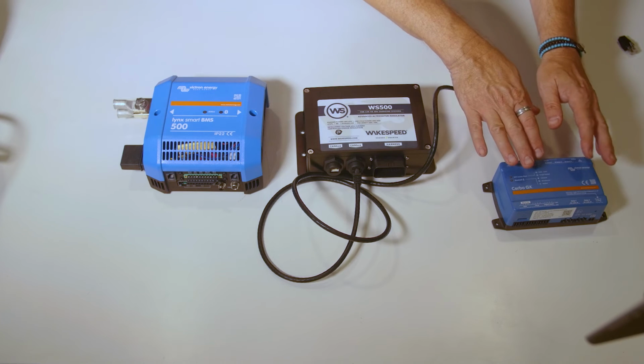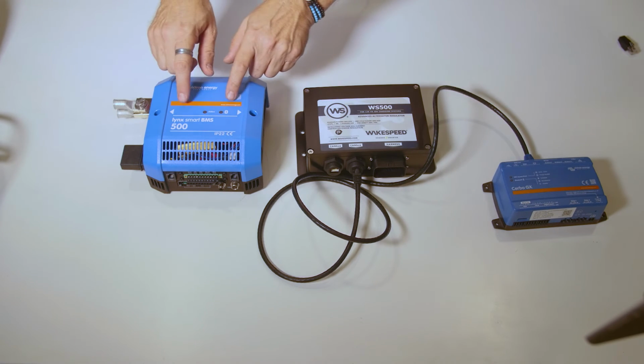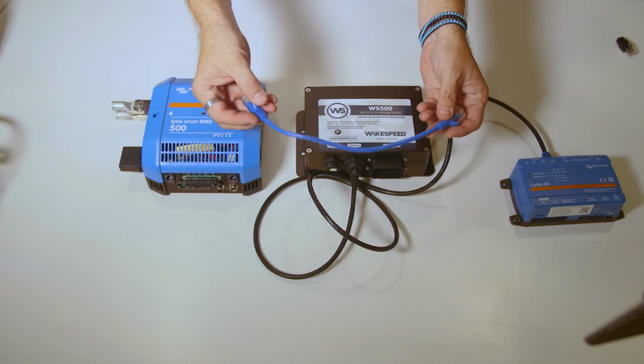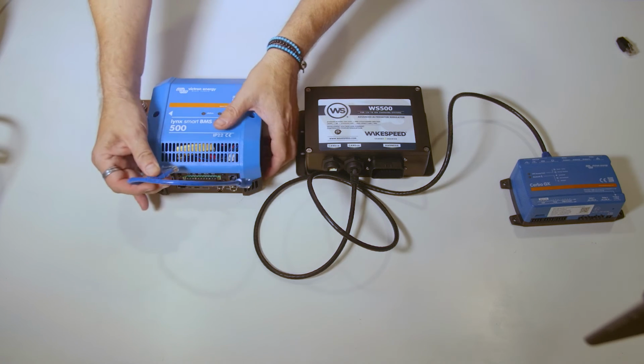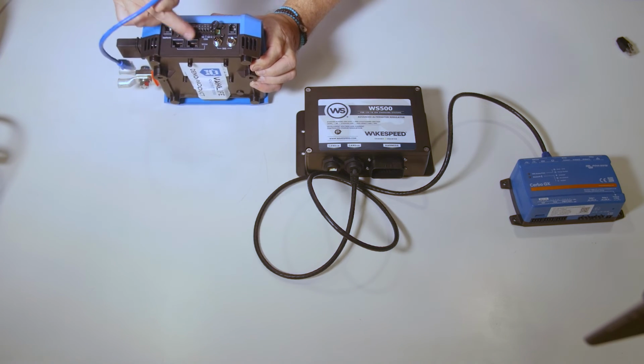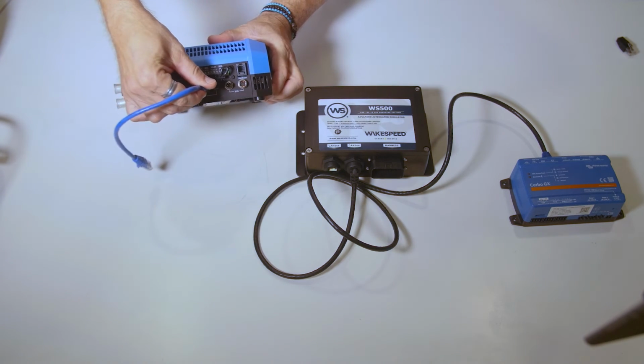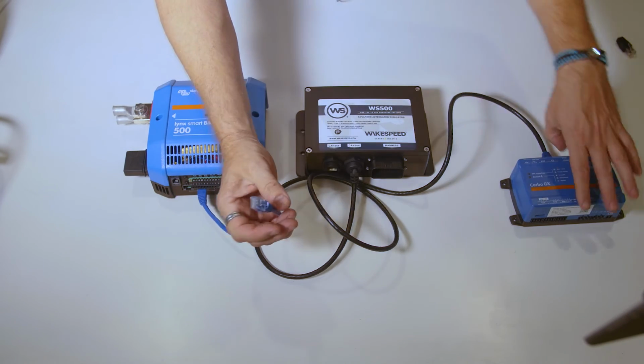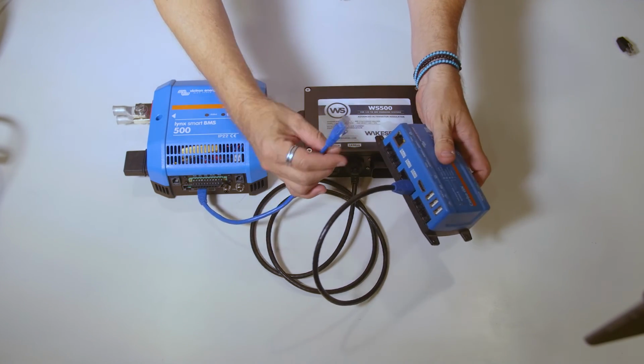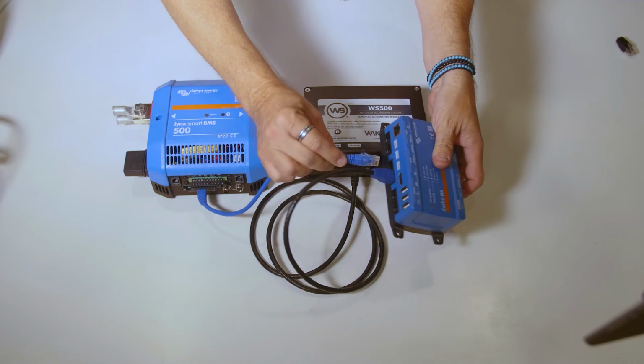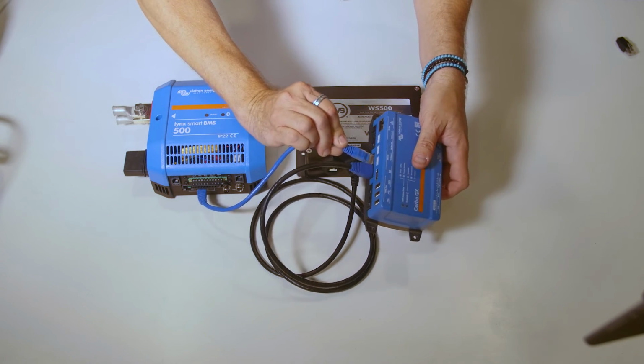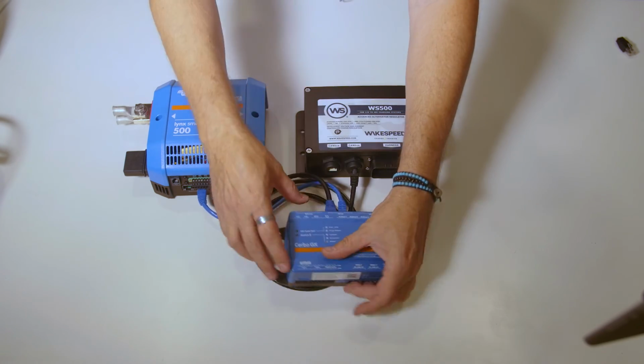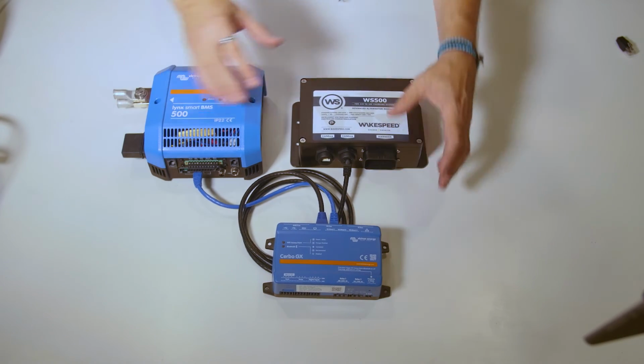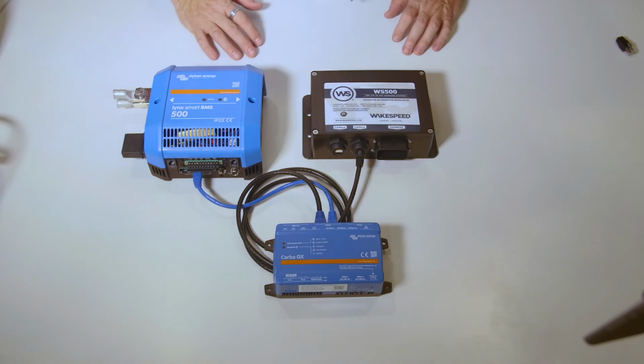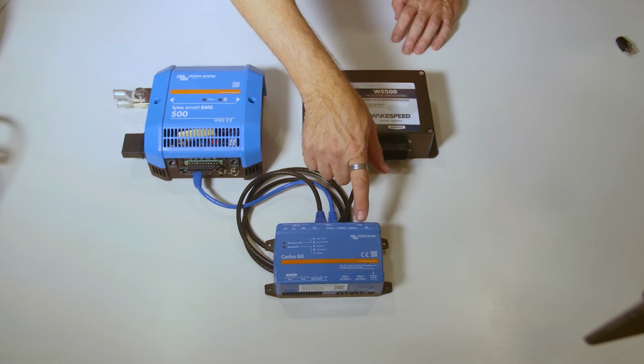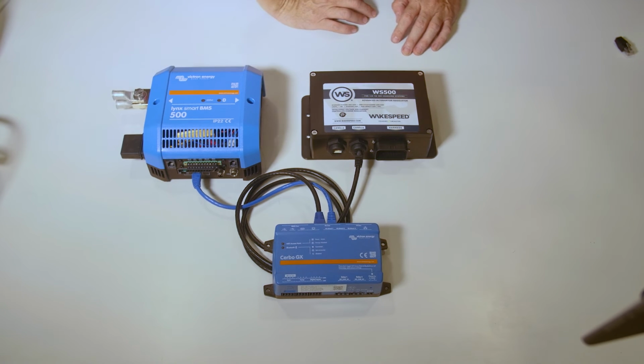Now we need to communicate between the Cerbo and the BMS. We have a rather short cable to do this. We're going to take one of the VE CAN ports on the Lynx BMS and connect it to the other port on the Cerbo GX. So we're getting somewhere now - that was the VE CAN port. We're not using the VE bus ports, and we're not using the Ethernet ports.